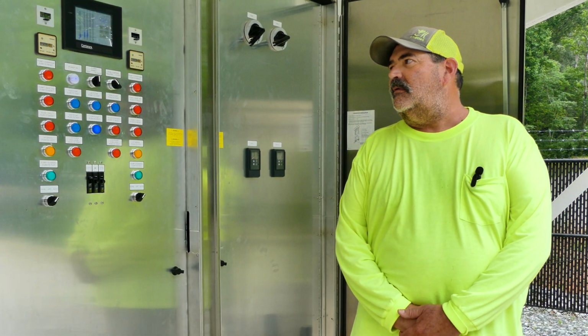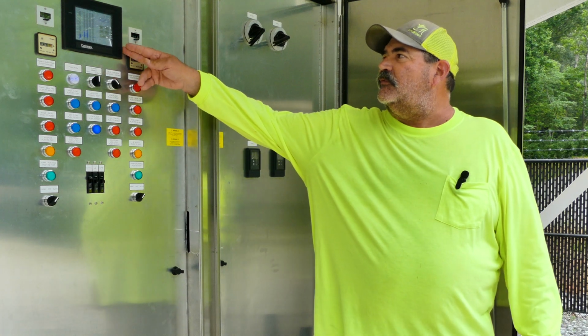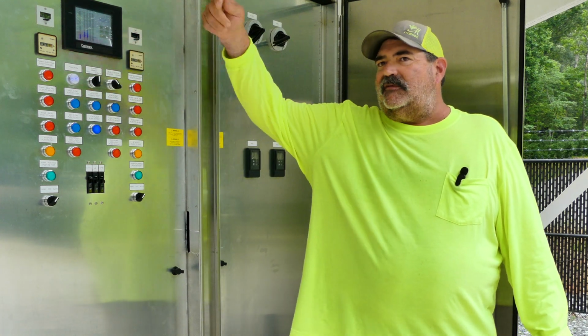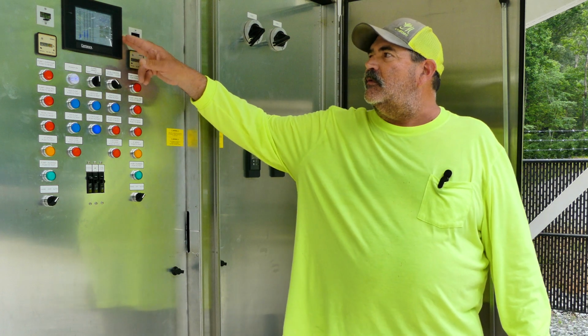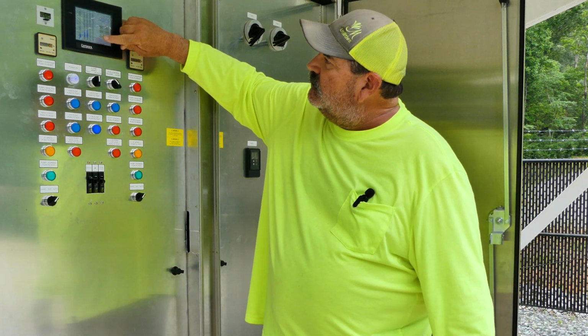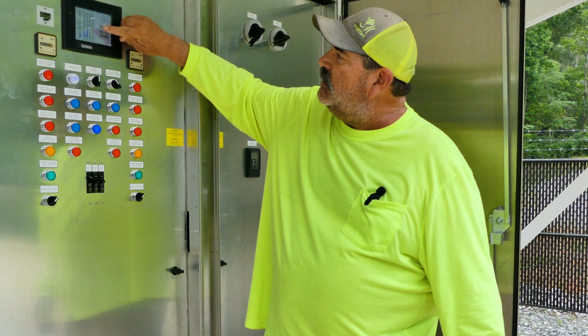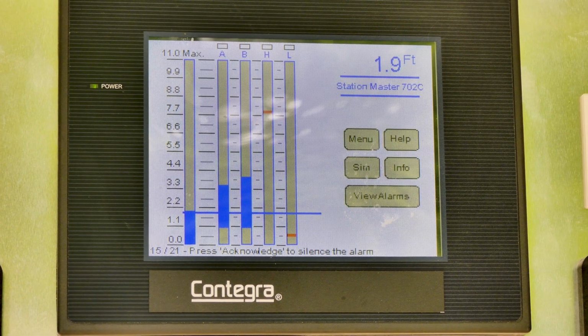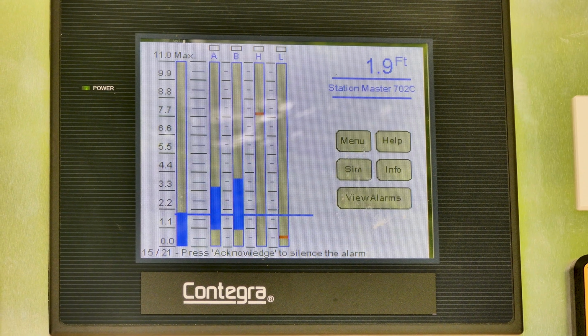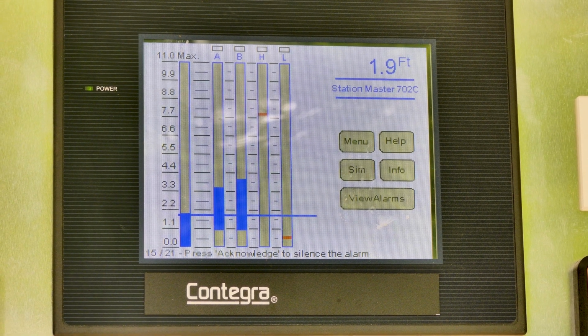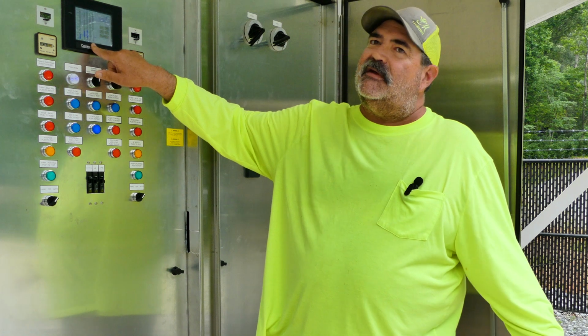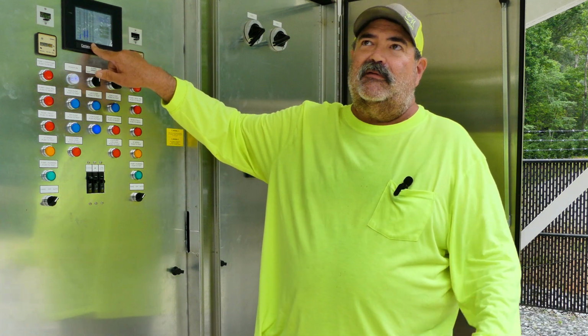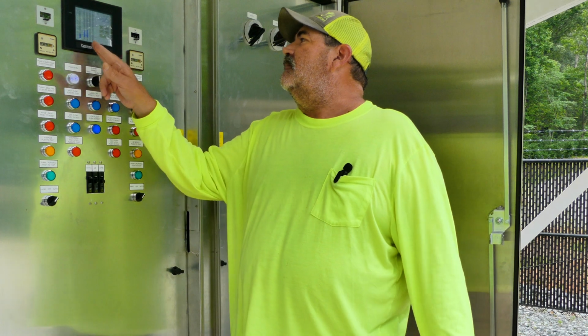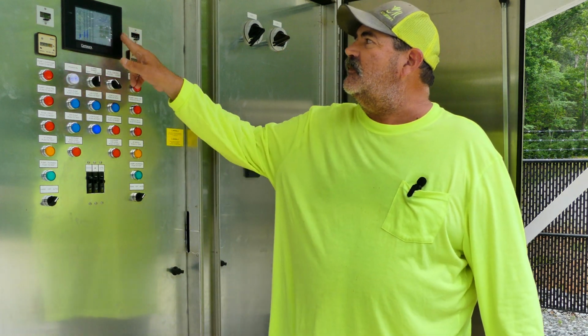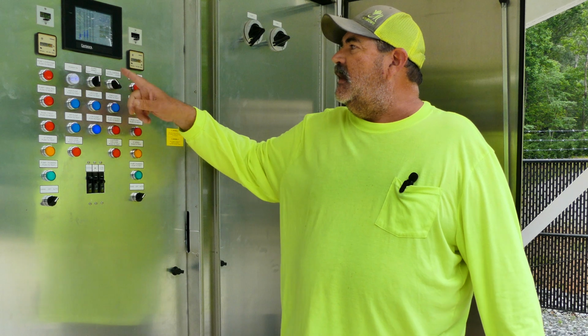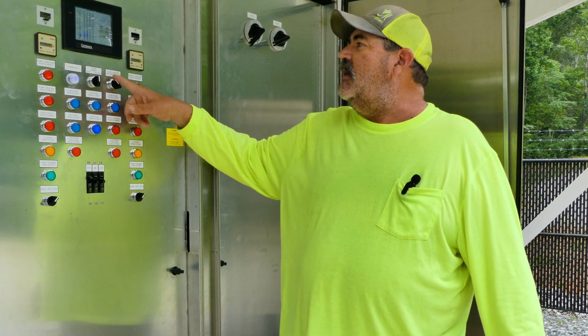We also have level transducers here, which is a transducer that goes into the wet well, uses water pressure, and this right here tells the pump when to cut on, when to cut off. You have two pumps. You have a lead pump and a lag pump or backup pump. At a triplex station, that would be a double lag or another backup. If something happens and this goes out, we go from transducer to floats.